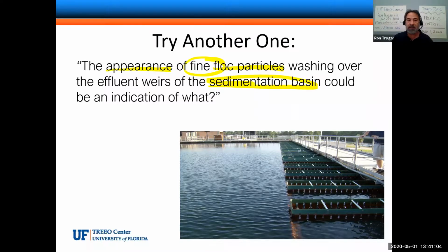The word fine doesn't mean like, oh, they're perfect, or oh, they're the best flock particles, and that's exactly what we want. In this particular case, the word fine means very, very small, very tiny, residual coagulant particles, if you will, almost like some of the aluminum sulfate has made it to the very end and it hasn't been precipitated out. So fine flock particles in this case mean very, very tiny, somewhat maybe turbid appearing flock particles that are going over the weir. So this should not happen in the sedimentation tank, obviously.